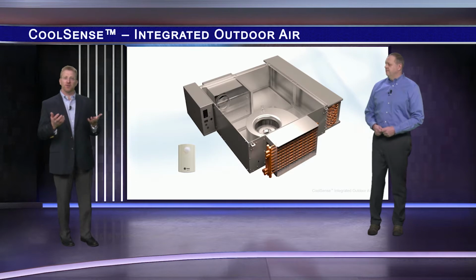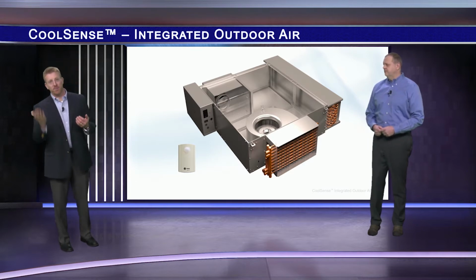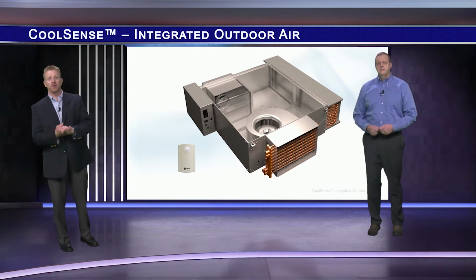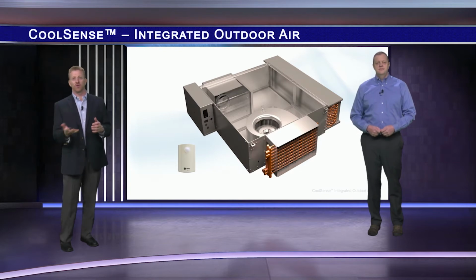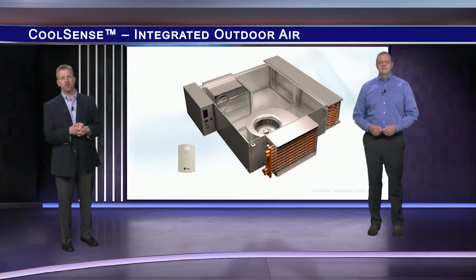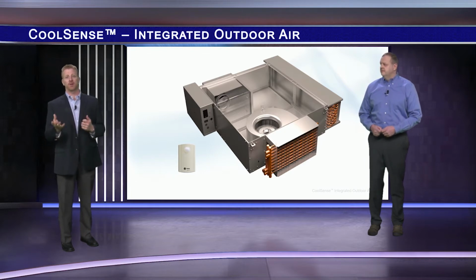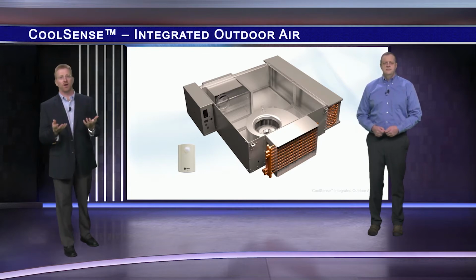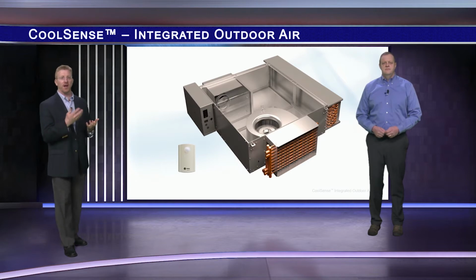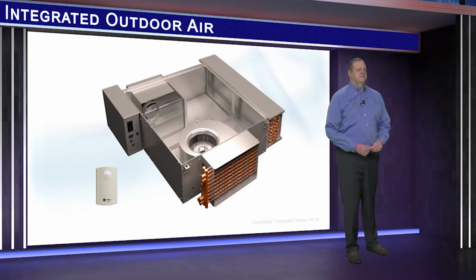And for those with the curious eye, there is a drip pan on both the bottom and the top of the coil. If you ever need to flip the box over during installation to better line up piping connections, the only thing you need to do is relocate the moisture sensor, a minor task. At this point, I'm going to turn it over to John to explain how the terminal unit is controlled.